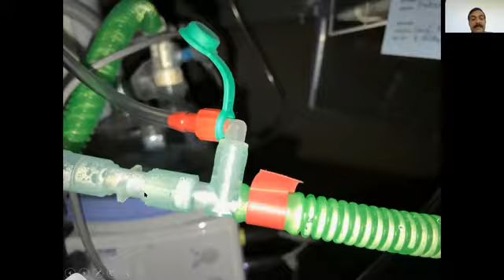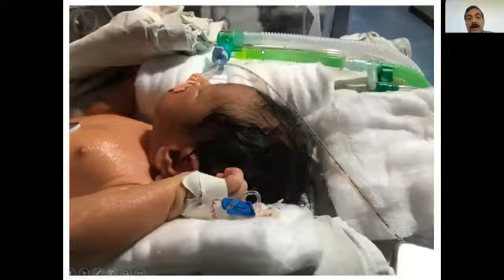This is where, immediately, the red indicator says that nitric oxide is delivered immediately after the humidification chamber. And this is the green part, where it is just connected to the proximal part of the inspiratory limb. And this is the gas. Once we fill this gas, the maximum capacity of the cylinder is about 950 to 1000 parts per million, and for the smaller cylinder, the capacity is about 900 to 950 parts per million.